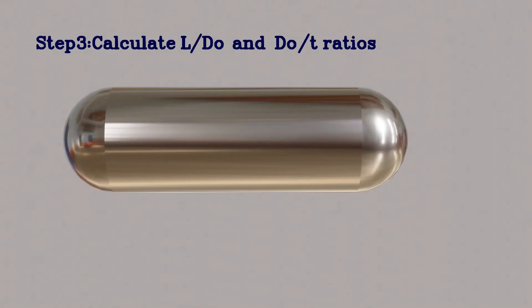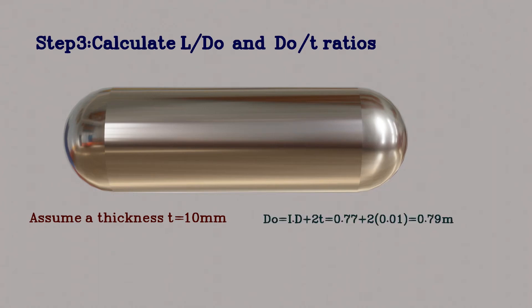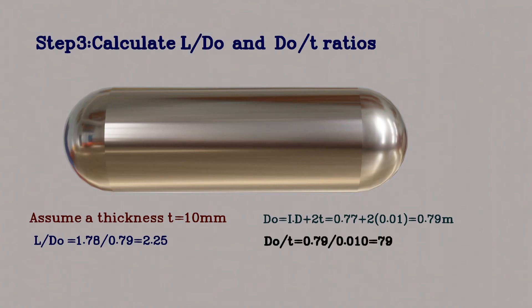In step 3, we calculate the L/D0 and D0/T ratios. Assuming a thickness T of 10 mm, we calculate D0 = inside diameter + 2t = 0.79 m. From this, L/D0 = 2.25 and D0/T = 79. These values are needed to find factors A and B in the next steps of calculation.